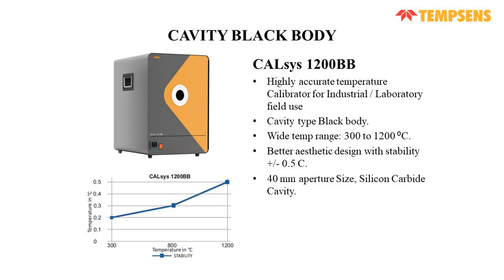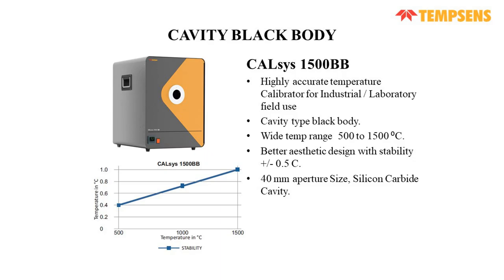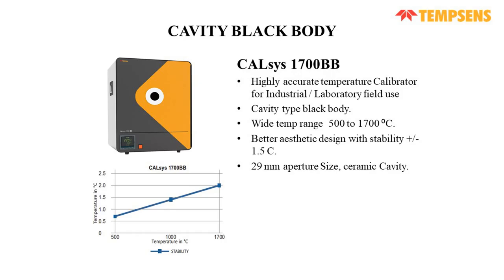Then we have cavity blackbody. The CALsys 1200BB is a cavity based blackbody, and it has a wide temperature range from 300 to 1200, and it has a stability of plus minus 0.5 with 50 mm aperture size. It uses a silicon carbide cavity. Then we have CALsys 1500BB, again a cavity type blackbody with 500 to 1500 as its temperature range, stability of plus minus 0.5, and 40 mm aperture size. Next we have CALsys 1700BB with a temperature range of 500 to 1700, stability of plus minus 1.5, and 29 mm aperture size. It incorporates a ceramic cavity.